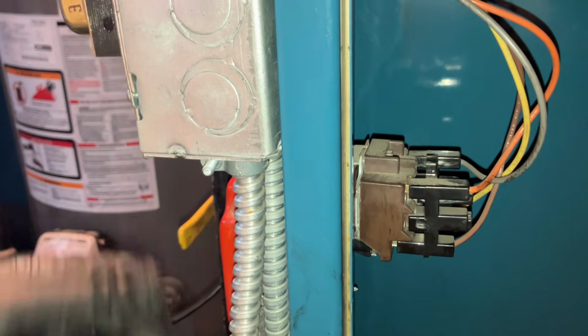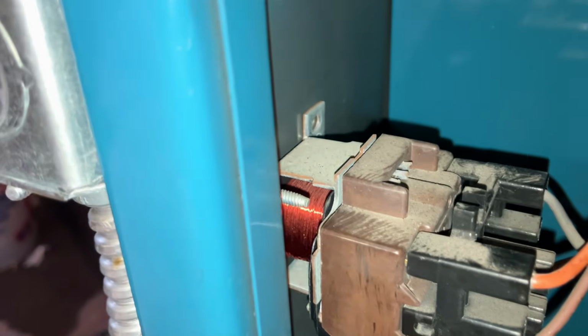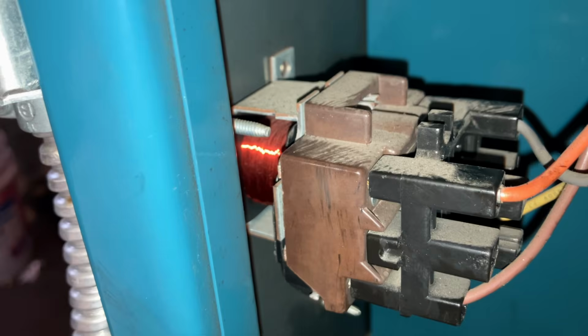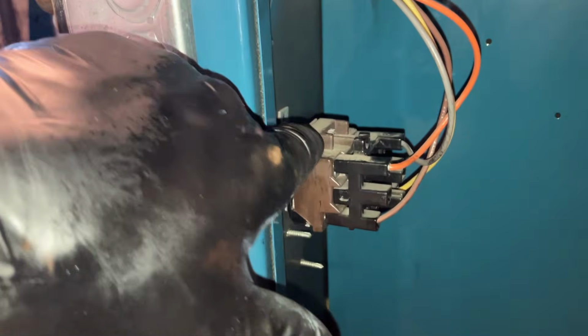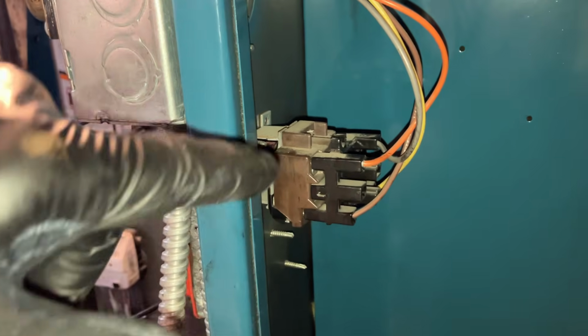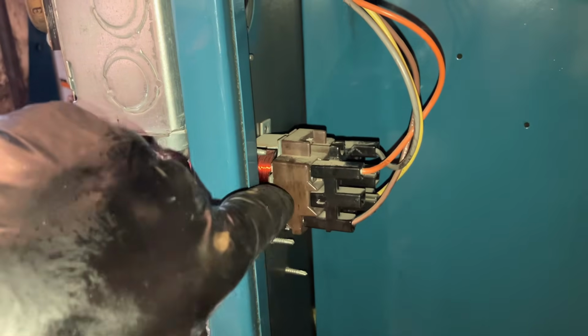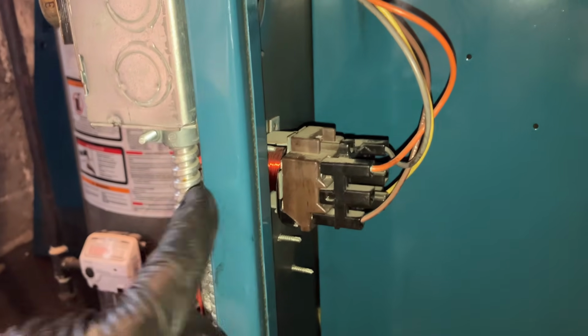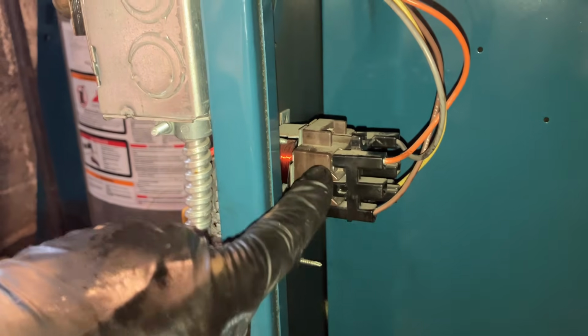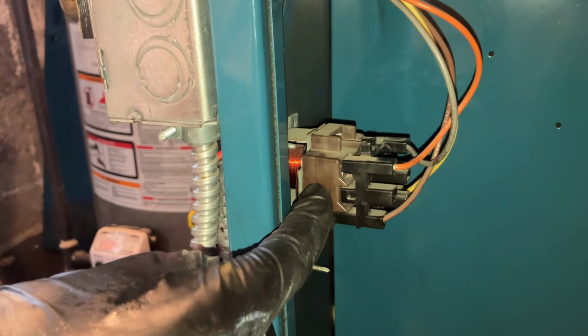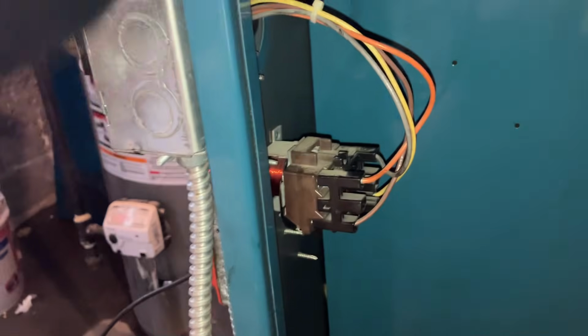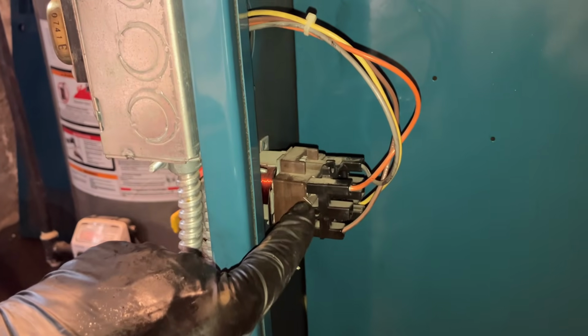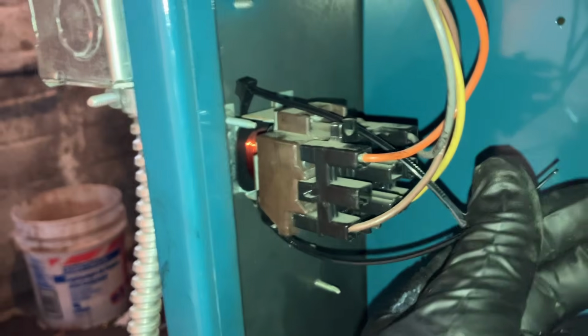There's that click. Now, when you work on these Burnham Independence boilers, you see that brown thing with the red coil, shiny coil? That's the thermostat relay. This is the harness. I'm going to take a zip tie and we're going to secure this, because that clicking on, off, on, off, on, off eventually separates the harness from the relay, and then you get a no heat call. It's a nuisance call, but the new Burnham boilers come with the zip tie now. It's crazy.